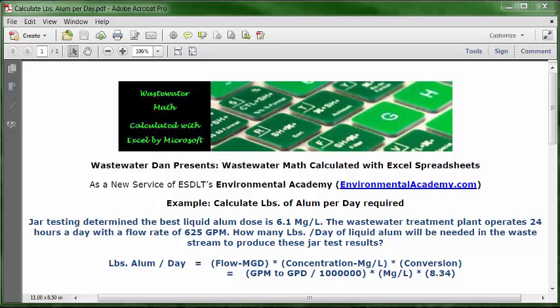The basic formula is: pounds per day equals flow in MGD (million gallons per day), times the concentration in mg/L (milligrams per liter) — so those two elements share the same expression of increments of millions — times the conversion factor from gallons to pounds. The conversion factor is fixed at 8.34, the mg/L comes directly from the problem data at 6.1, and we need to take the flow in GPM, convert it to days, then divide by one million to express it as MGD.